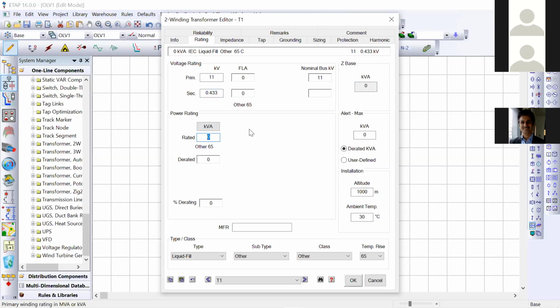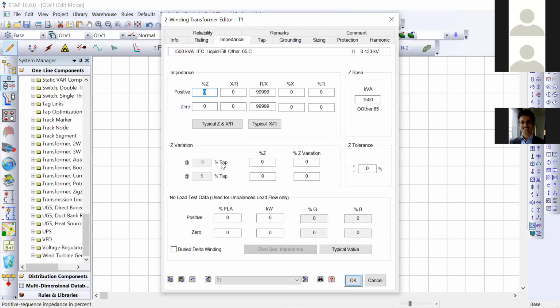So rated, say for example, I am taking a 1500 kVA transformer. The rest of the parameters it has calculated automatically, and I don't need to bother for other elements. So only the important parameters we have entered. Now it comes to its impedance data. For a 1.6 MVA, 1600 kVA transformer, generally the impedance is in the range of 5 to 6. So I am taking 6% impedance. X by R ratio I am taking 15. These are the general data you have to obtain from the transformer manufacturer. We regularly deal with this data, that's why we know.